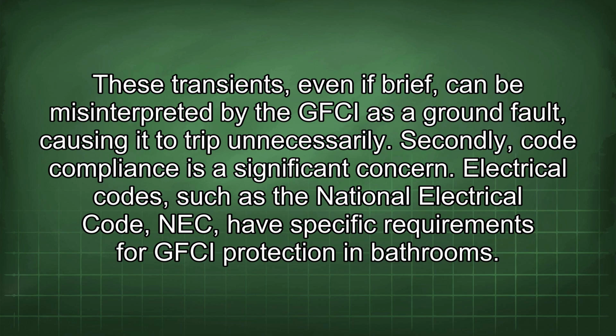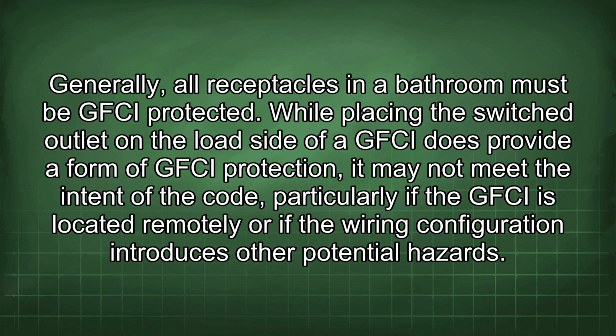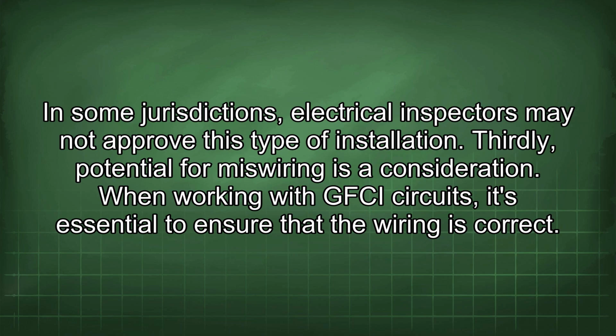Secondly, code compliance is a significant concern. Electrical codes, such as the National Electrical Code, NEC, have specific requirements for GFCI protection in bathrooms. Generally, all receptacles in a bathroom must be GFCI protected. While placing the switched outlet on the load side of a GFCI does provide a form of GFCI protection, it may not meet the intent of the code, particularly if the GFCI is located remotely or if the wiring configuration introduces other potential hazards. In some jurisdictions, electrical inspectors may not approve this type of installation.